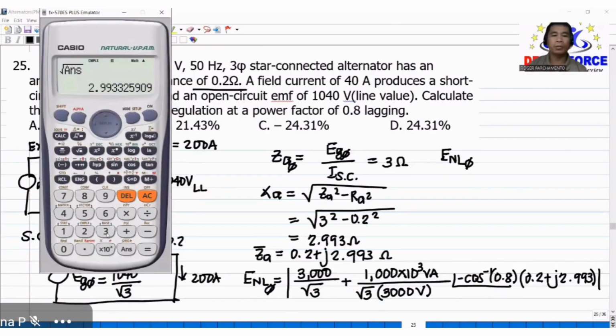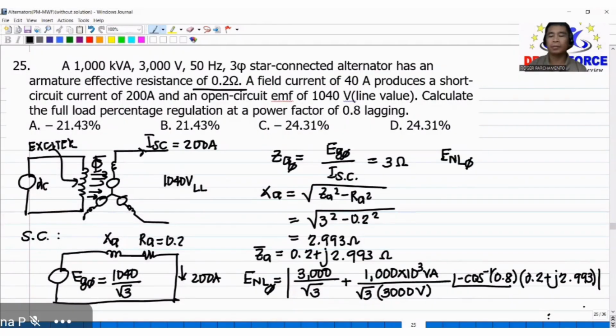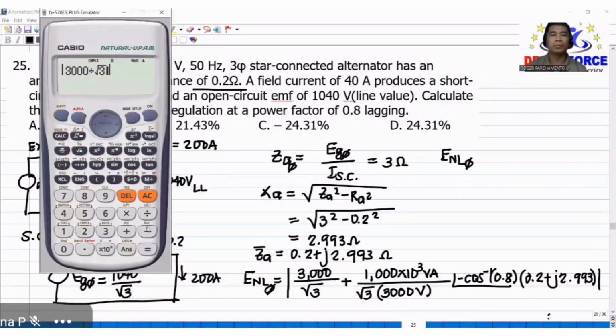Then magnitude, what is the E no load per phase? The E no load per phase is equivalent to the magnitude of 3000 divided by square root of 3 plus the current 1 million divided by square root of 3 times 3000. So we are adding vectorially, so we will include the angle of the current, negative arc cosine of the power factor 0.8, times 0.2 plus 2.993J. So 2153.399.